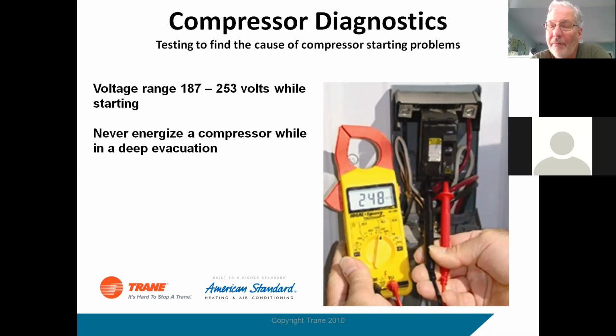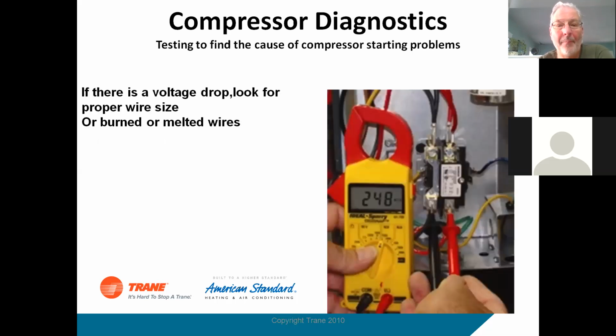Just make sure we have a voltage that is between that 187, and I think 187 is a little on the low side. A lot of manufacturers will say 197, which I would tend to agree with. But definitely at 187, you're going to have issues with units not starting. If there's a voltage drop, look for proper wire size, look for melted wires. Just kind of do a visual inspection.